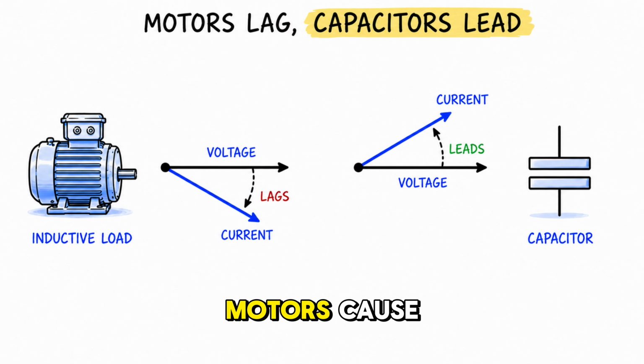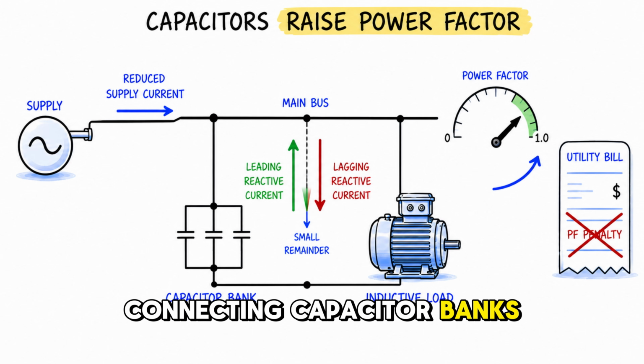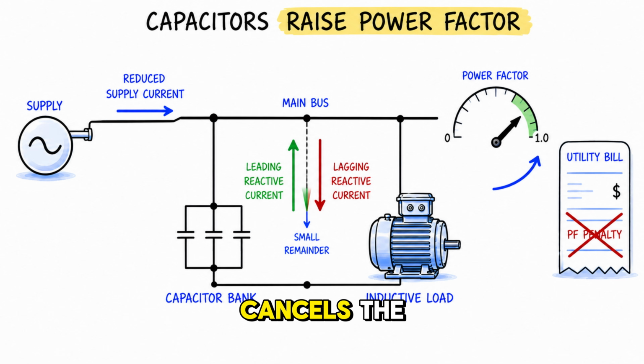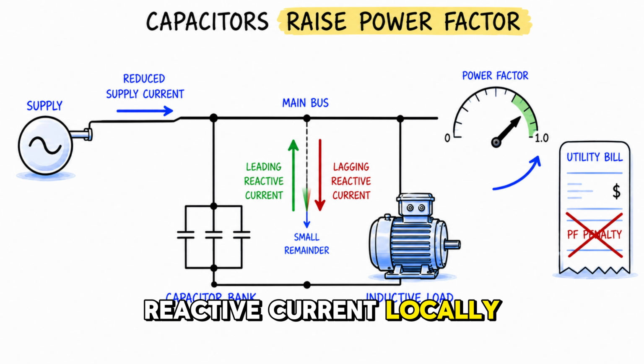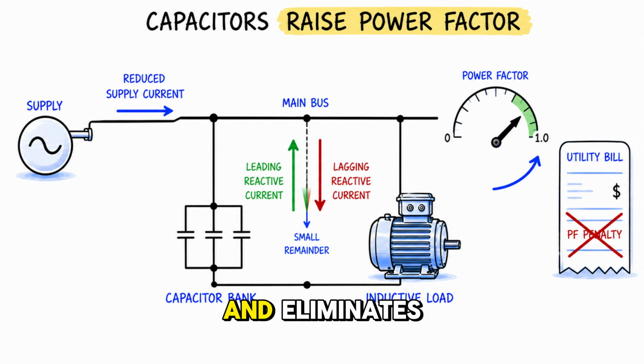Inductive loads like motors cause current to lag voltage. Capacitors cause current to lead voltage. Connecting capacitor banks in parallel with inductive loads cancels the reactive current locally. This raises the power factor toward 1 and eliminates penalty charges from the utility company.